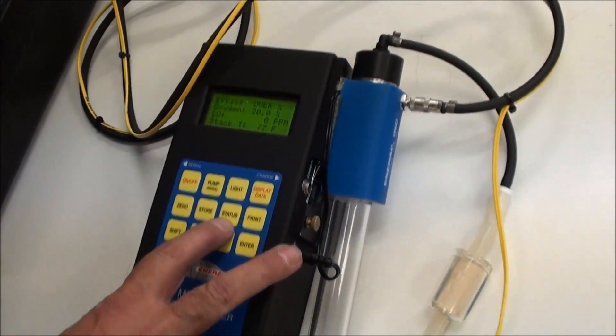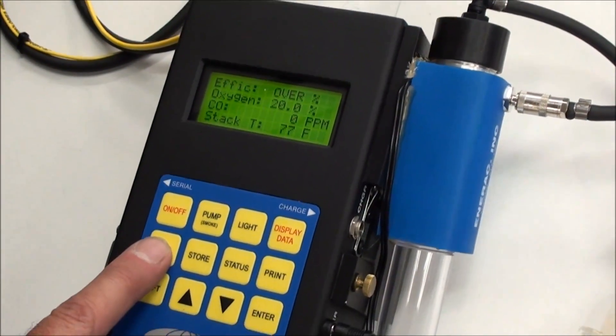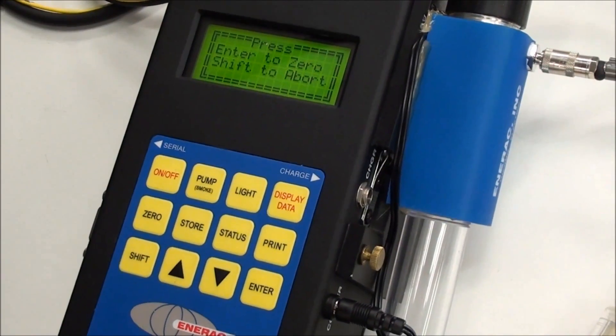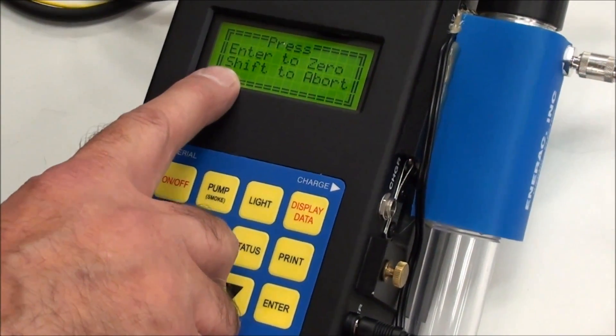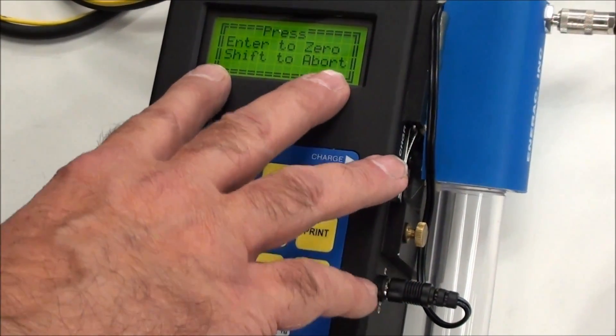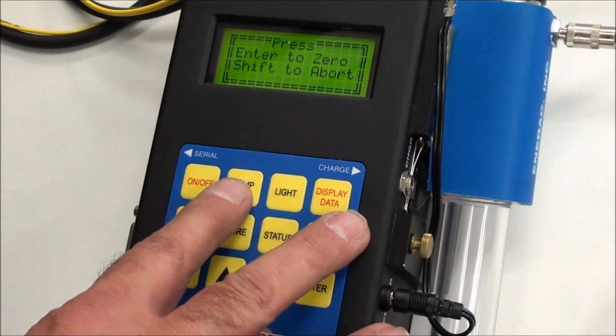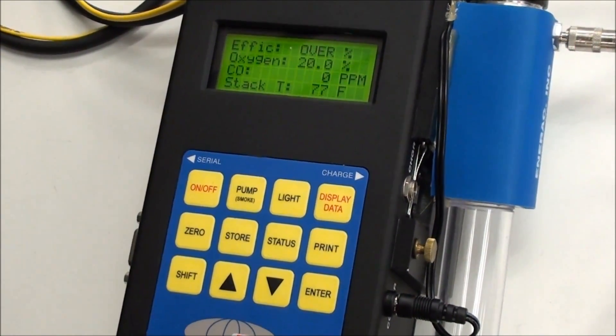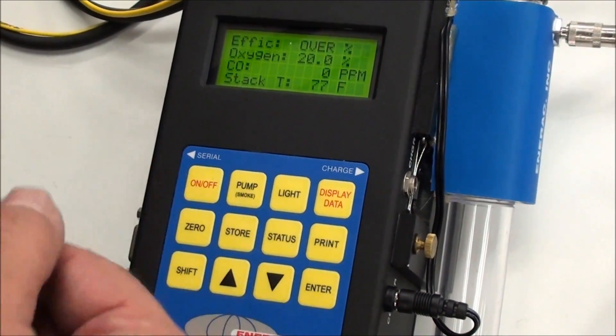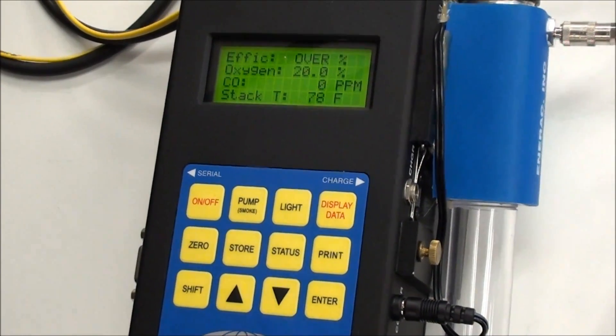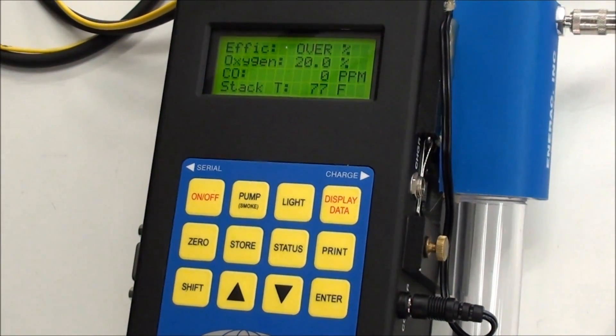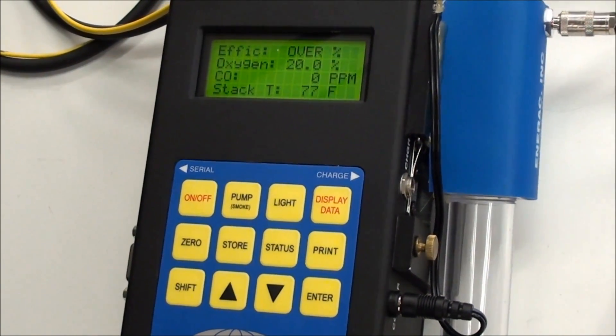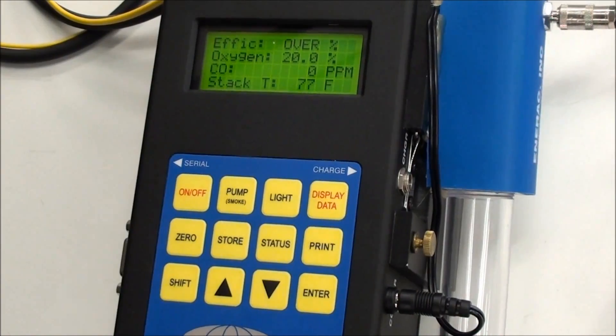Now, at this point, you're pretty much ready to go. You will hit the zero button, and it'll say enter to zero or shift to abort. There's really no reason to abort at this point. If you're taking readings, and you accidentally hit the zero button at that point, now you want to shift to abort, because if you run the auto zero, and there's any gas present in the system, it will create erroneous readings on your sensors. You want to make sure that when you zero it, you're in a clean atmosphere, a clean office, or outside.